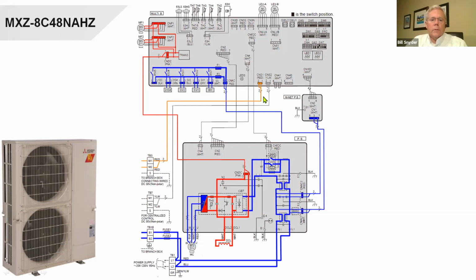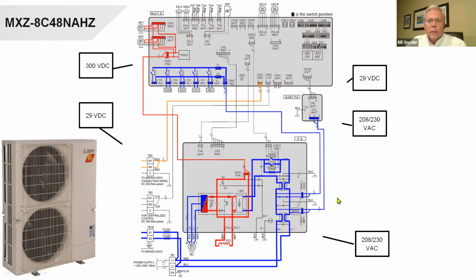And this board here is powering the MNet. Let me click this one more. We come in here with 208, 230. We come out of here with 29 volts DC that goes out to this terminal, which is the 16 gauge twisted shielded pair of wires that goes out to the branch box. Also down here, the line voltage comes into the board. It also comes up here and goes to this set of terminal blocks, PB1B, which is to the branch box.